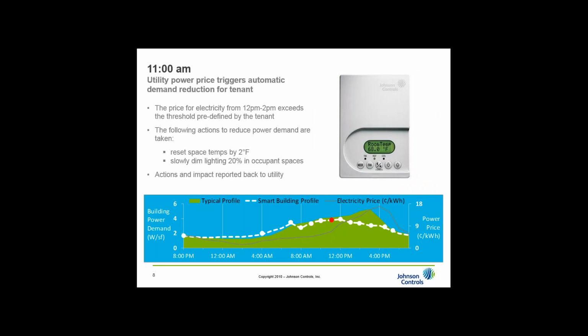11 a.m., the utility power price triggers an automatic demand reduction for the tenant. So the system is already going to automatically reduce the temperatures in the spaces a few degrees. It's going to start to lower the lighting so that when peak demand hits at 12 o'clock, the building has already started to reduce consumption. And that typically doesn't affect the tenants much because the building has already had a pre-cooled or preheated space, so they're usually comfortable. And if everybody knows that in these couple hours we're trying to save energy, we've reduced or raised the temperature a couple degrees, the lighting is dimmed a little bit, even shut off in some areas that are not being used, all to avoid those extremely high peak demand charges.